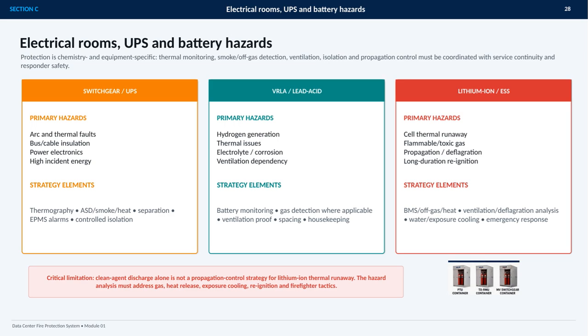Lithium-ion systems can experience cell thermal runaway, flammable or toxic gas release, propagation, deflagration, and long-duration reignition. Protection therefore requires coordinated battery management, off-gas and heat monitoring, ventilation and deflagration analysis, exposure cooling, and emergency response planning. The hazard analysis must also account for heat release, reignition, and firefighter tactics, not just the initial alarm or discharge.